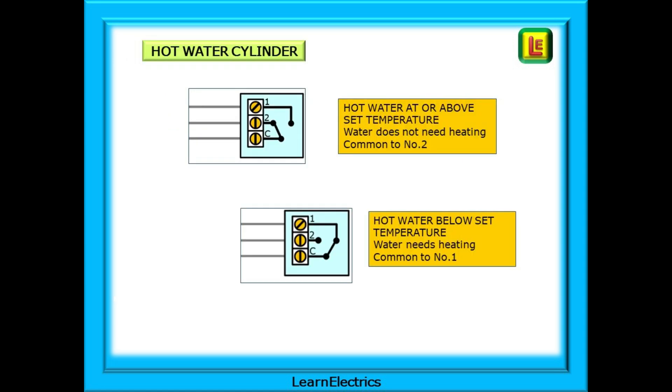The thermostat in the hot water cylinder works in a different way. It has three terminals and all three terminals are needed. When the hot water is up to temperature, the C or common terminal and 2 are closed. If the water temperature is below the set value, the switch changes position and the common is connected to terminal 1. Up to temperature, C and 2 connected. Below set temperature, C and 1 connected.